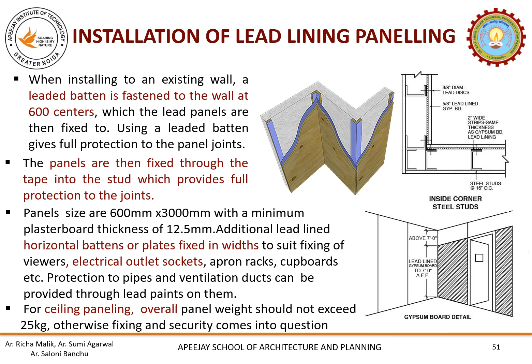Prefab lead panels are a simple alternative to fixed permanent wall shielding. This is an easy, clean, and efficient method of non-altering rental spaces or converting existing rooms to a certified radiation protected X-ray rooms. As you can see in the picture, you can see the corner detail how the two panels can be fixed. Then the bottom detail, that bottom floor plate is there on which through drill we mount the partitions. Then how it will look in totality.